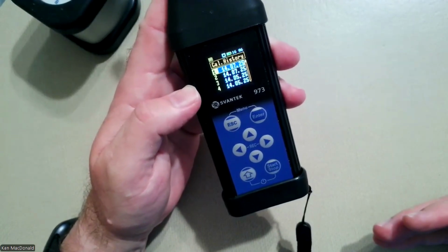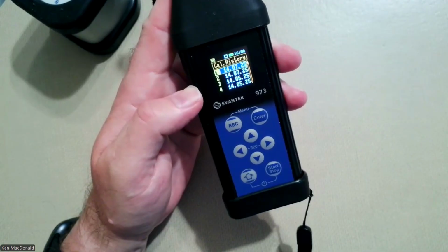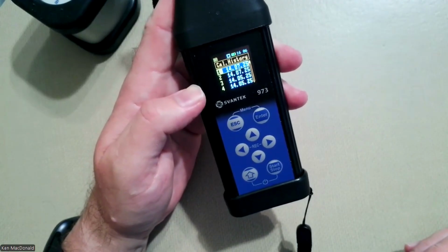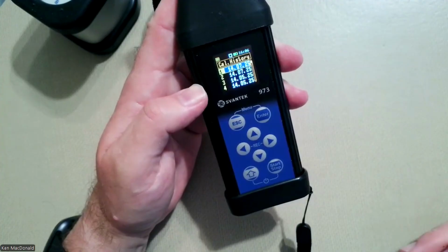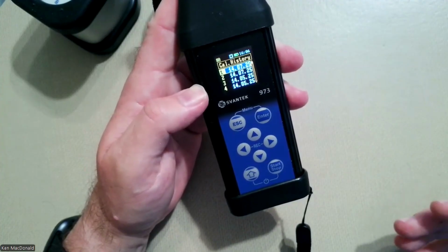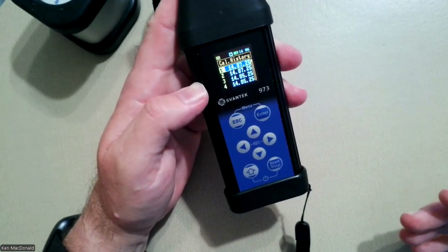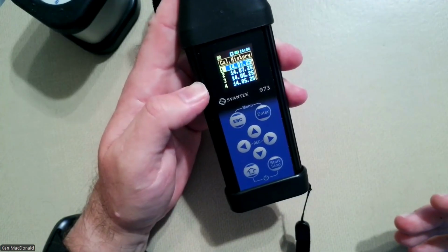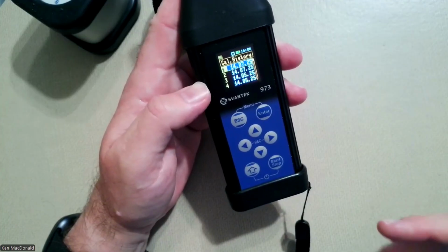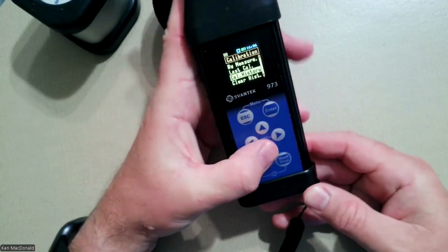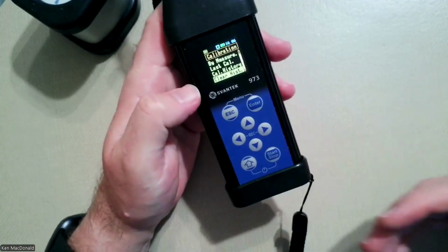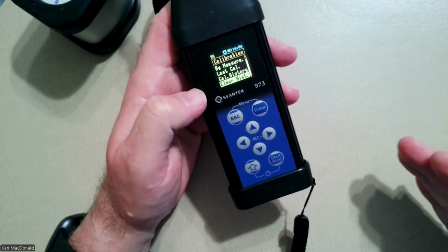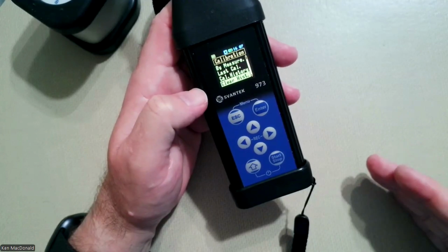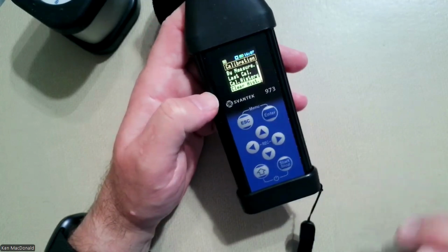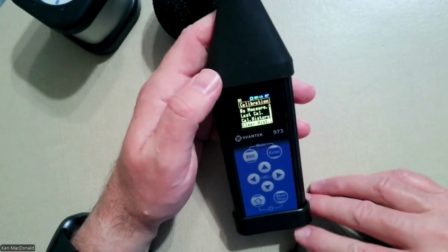Now, sometimes a post calibration is required where you've done this. You should do this calibration before doing any measurements each day. Usually once a day is okay, or if the unit's dropped or there's any issue, you may want to check the calibration. For some applications, you want to do your measurements and come back and then put the calibrator back on and do a post calibration. And you could also do that, and it would compare. That way, you'd know if the post calibration is close to the initial calibration. You know your data is good. So that basically covers the calibration.